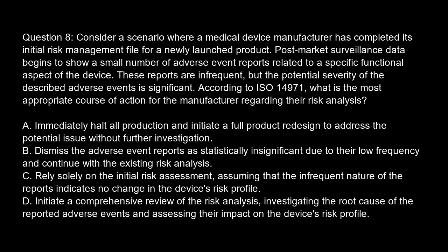Option A. Immediately halt all production and initiate a full product redesign to address the potential issue without further investigation. Option B. Dismiss the adverse event reports as statistically insignificant due to their low frequency and continue with the existing risk analysis. Option C. Rely solely on the initial risk assessment, assuming that the infrequent nature of the reports indicates no change in the device's risk profile. Option D. Initiate a comprehensive review of the risk analysis, investigating the root cause of the reported adverse events and assessing their impact on the device's risk profile.